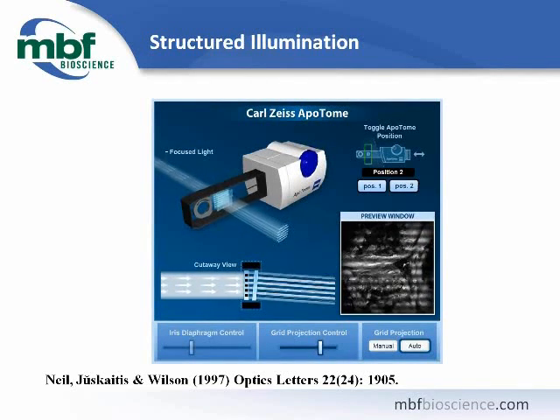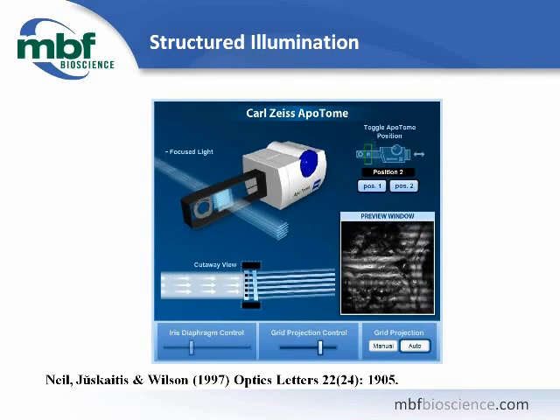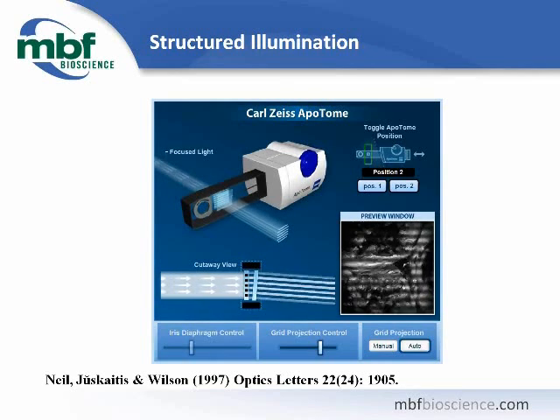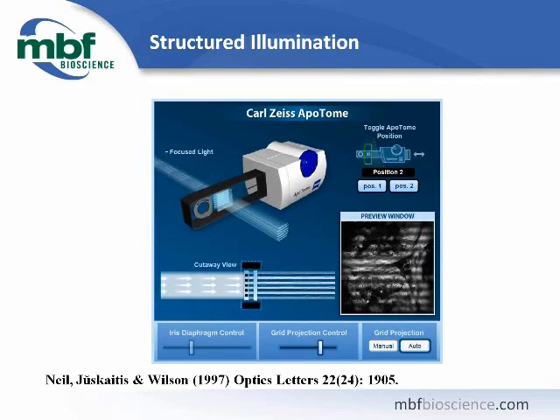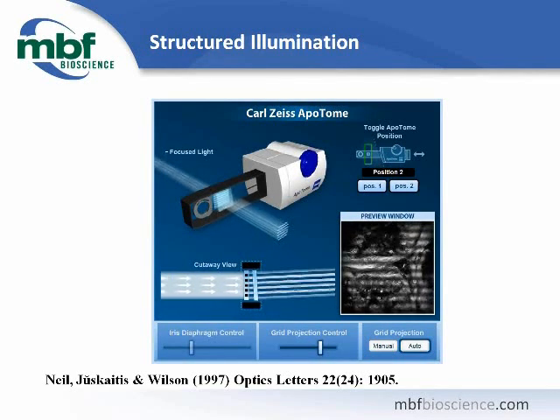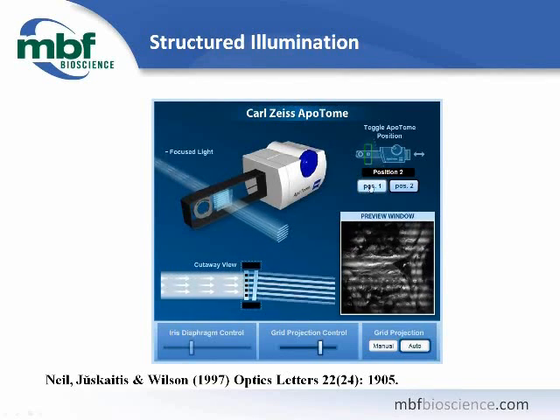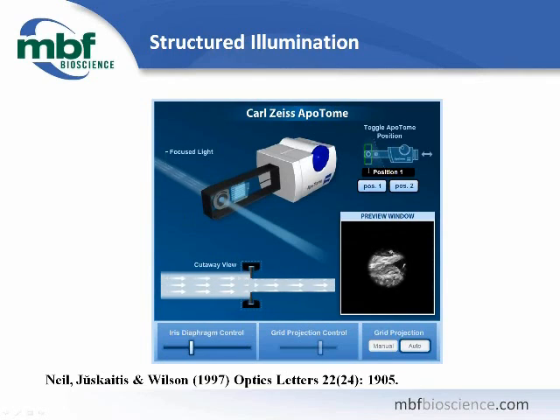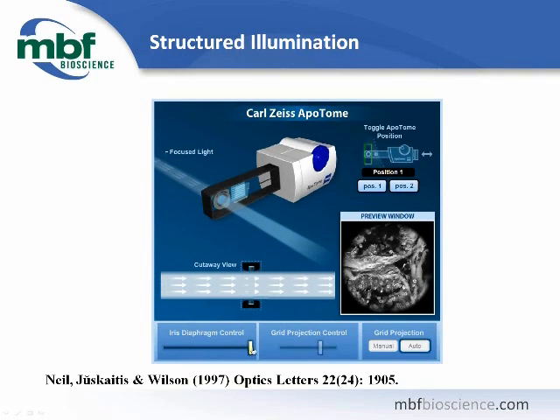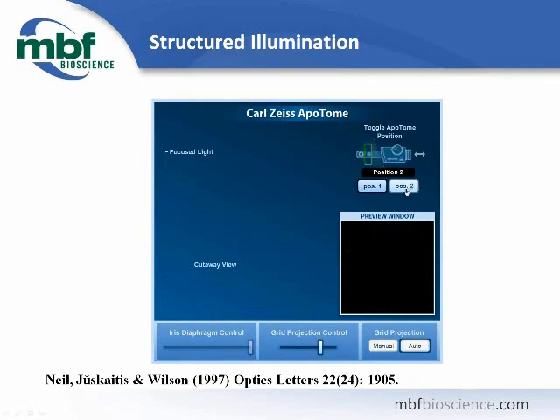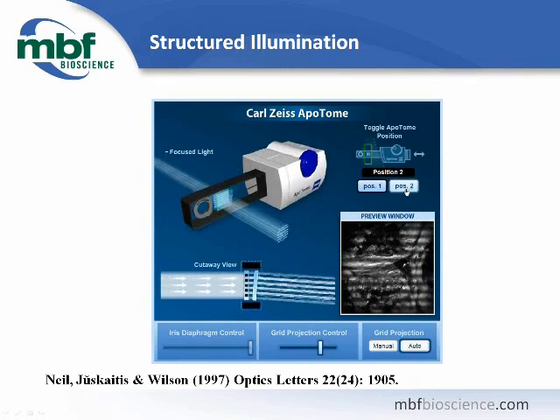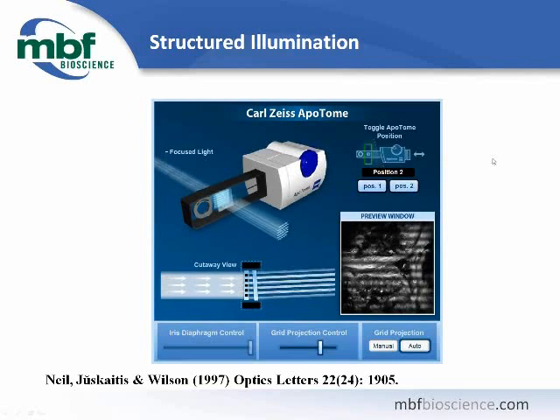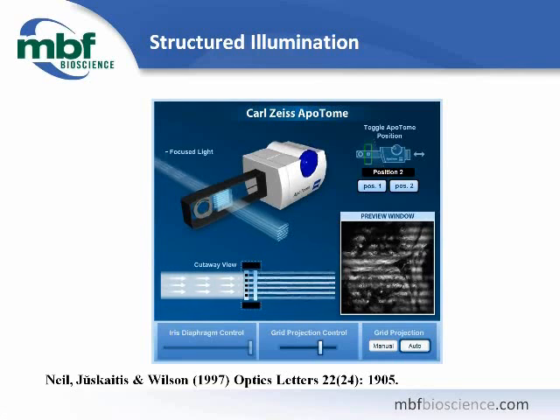Here is a nice animation of the ApoTome at work, graciously provided by the folks at Zeiss. This shows what you will see in live video with the ApoTome set up and ready for calibration. There are two positions for the ApoTome when it is in place on the microscope. Position 1 presents an iris diaphragm in the reflected light path for standard wide-field mode imaging. Position 2 presents the grid insert, which projects the grid pattern onto your specimen for ApoTome mode imaging.